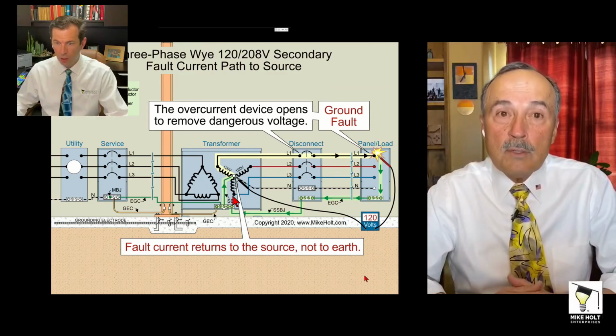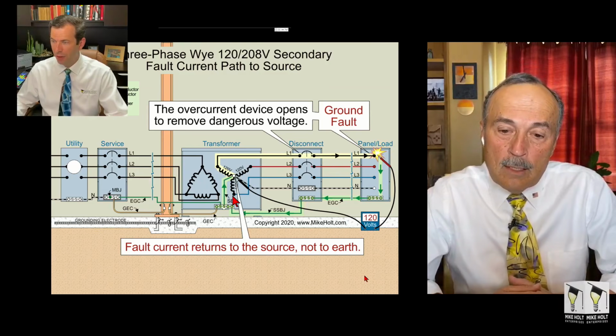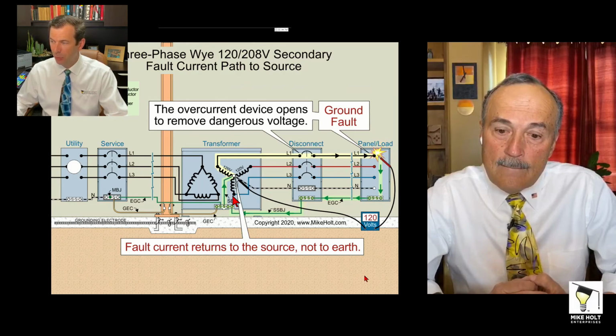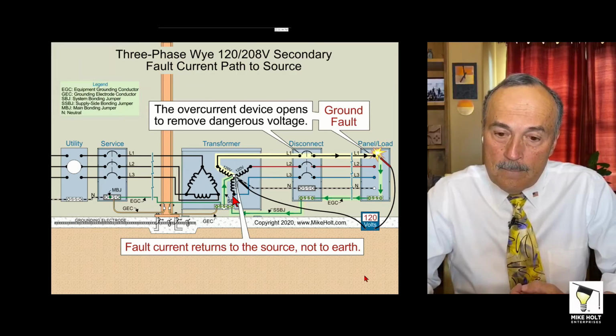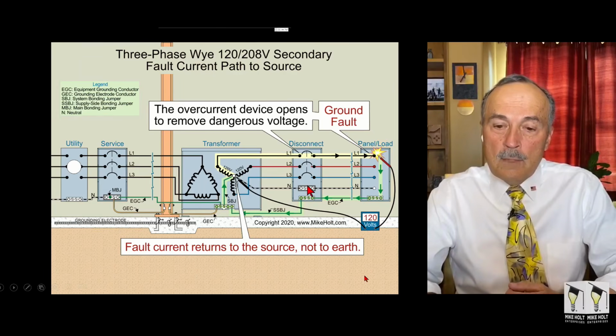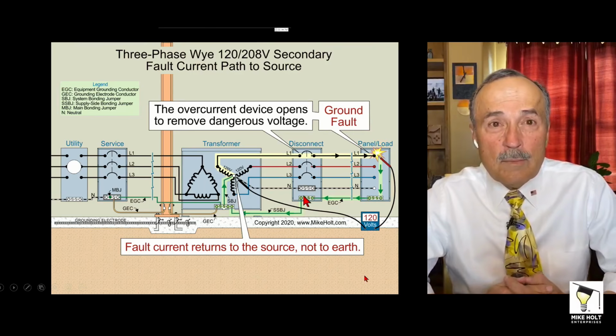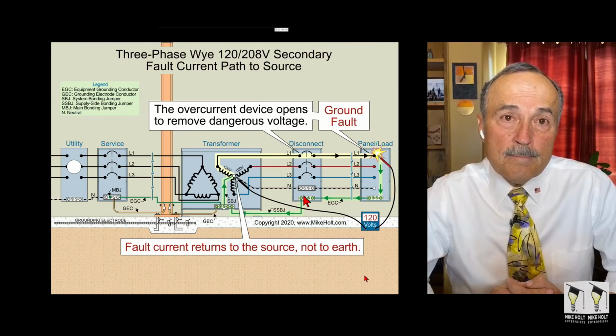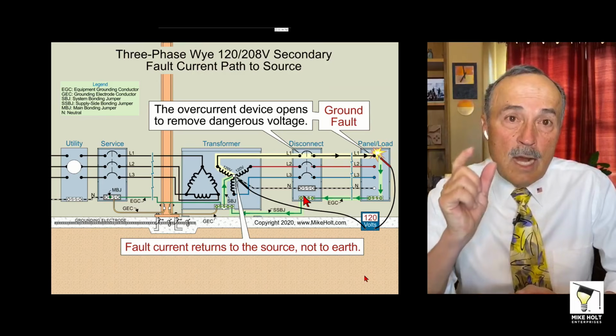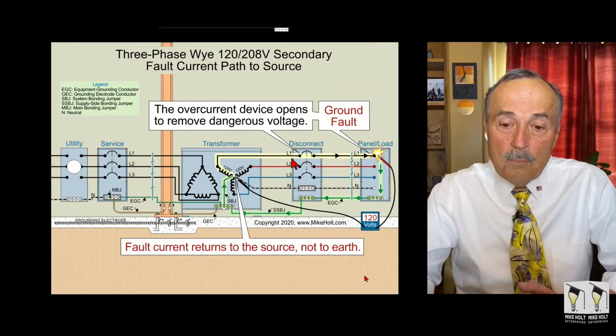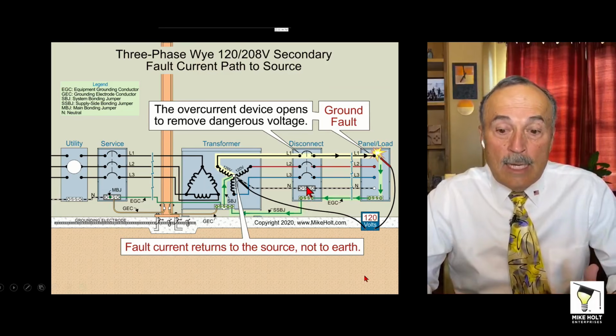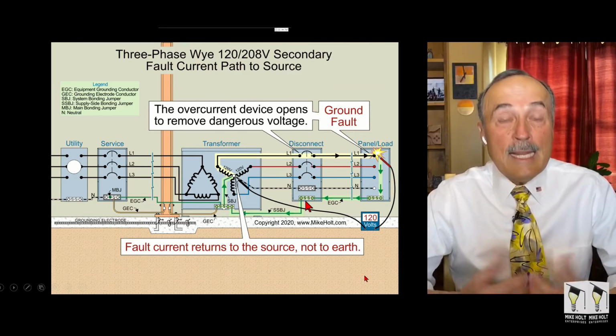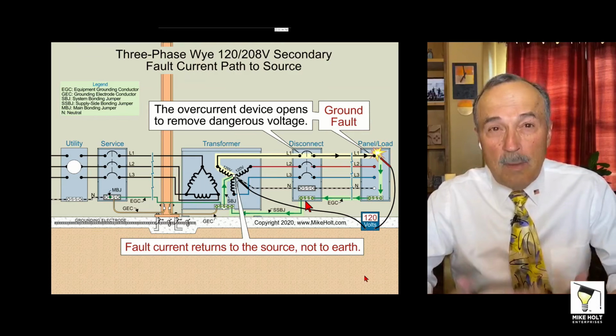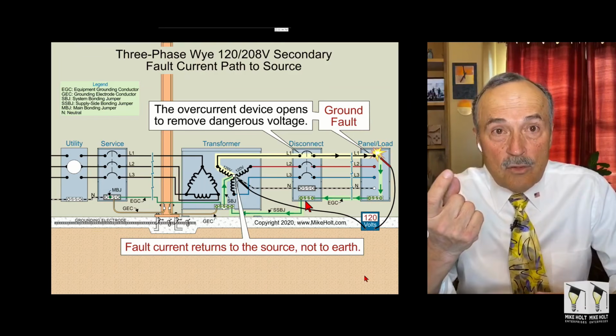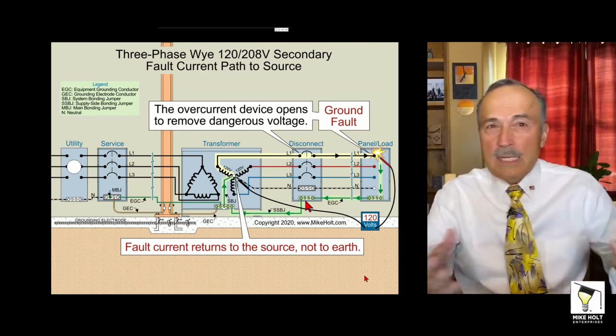Okay, before you move from that graphic, if the disconnect is used for the system bonding jumper, does it need to be service entrance rated? If you're going to put a system bonding, listen, all equipment is going to be rated for service equipment. So if you're going to have a disconnecting means, it's going to come with a strap. And if you plan on putting the system bonding, if you're going to bond that neutral to the enclosure, then that enclosure has to be suitable to have the neutral bonded to it, which means it has to come with a strap. So this isn't a complicated thing.